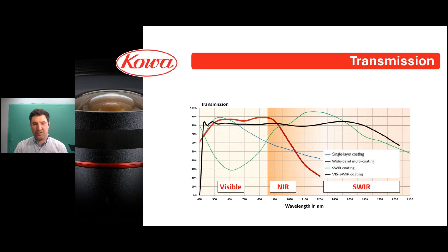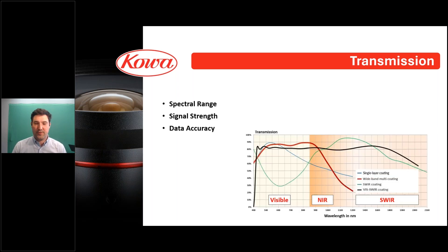Careful selection of lenses with suitable transmission properties for the intended spectral range is essential for optimizing hyperspectral or multispectral imaging systems. Lens transmission can affect hyperspectral imaging in several ways. The lens material and coatings need to transmit light within the spectral range of the hyperspectral camera you're using. If you have poor transmission outside the visible spectrum, your work can be hindered, especially in areas like near-IR or SWIR. These different coatings are optimized for transmission in different bands, as you can see on the graph.